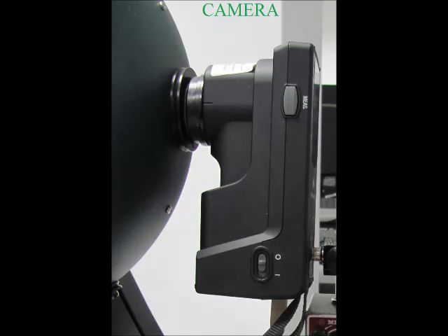Camera / photo detector. They are measuring instruments which can be interfaced with a PC to display different types of data, for example, a spectrum graph, and so on. The camera filter and lens must be fitted nicely into the port of the integrating sphere. This is to prevent light from leaking.